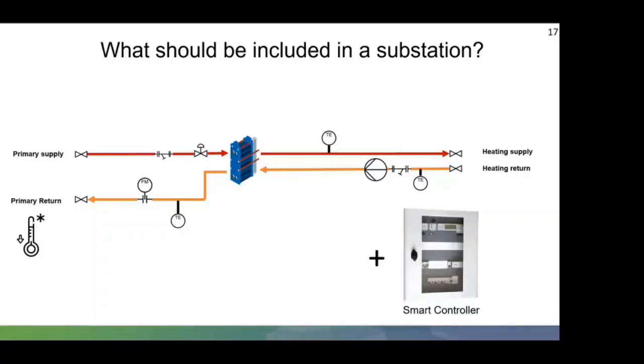So you tell us the design of the building, the capacity required, and then we can size up the heat exchangers, the valves, the controller. And with everybody moving now to apps or online, rather than being connected to a BMS system, there are ways of connecting buildings or heat stations up to a network so that the system can be monitored. And then you can put in things like weather compensation, you can put in flow and return temperatures, you may get warmer days, colder days. You can look at the orientation of the building: is one side of the building colder than the other, a north facing building where it doesn't get a lot of sunlight. So a lot of that can be taken into consideration.